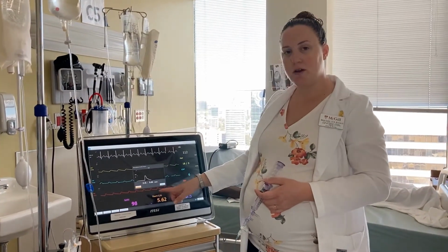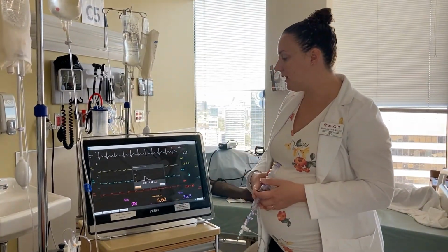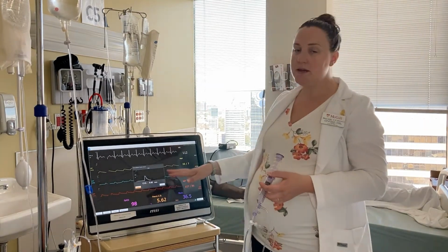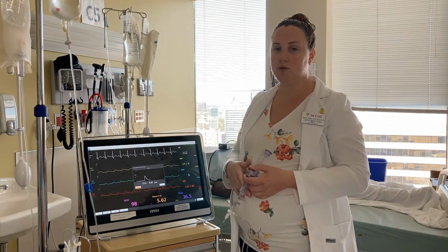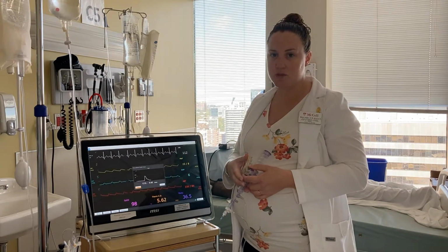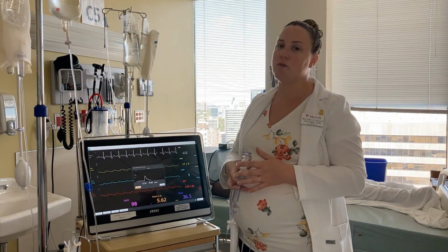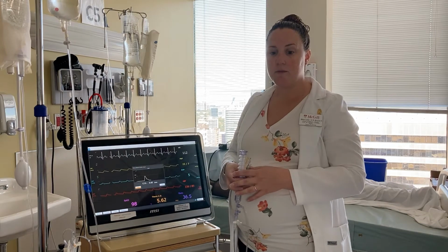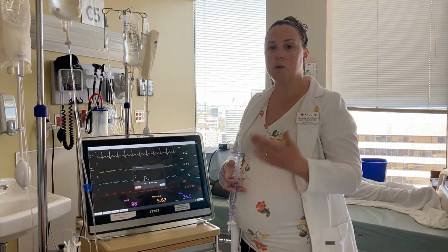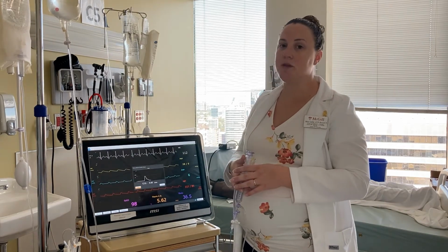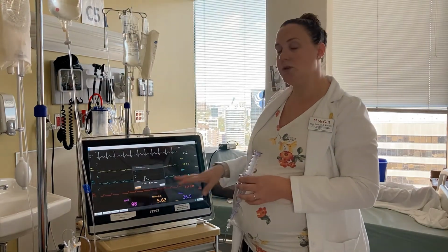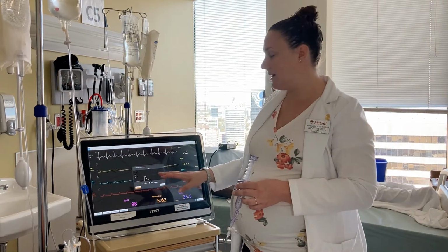So after measuring our cardiac output, you can see that we got a cardiac output of 5.62 liters per minute. So from here, we would be doing multiple measurements to try and get an average. So we could do 2 to 3 measurements because there may have been other forces that could have affected the measurement itself. So either we would have pushed too slowly, or we weren't steady, or maybe the patient took a breath sooner than we thought, so it interrupted our exhalation. So we do want to take 2 or 3 measurements and take an average.